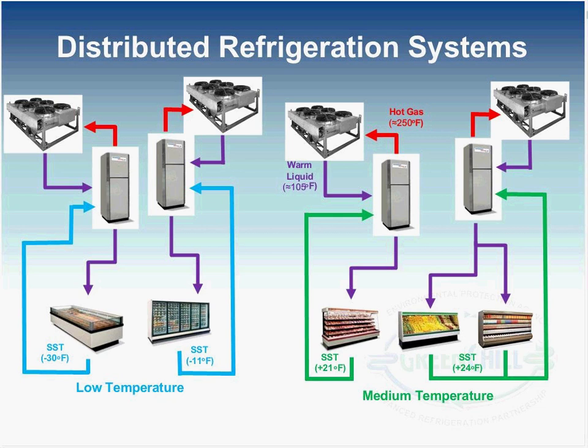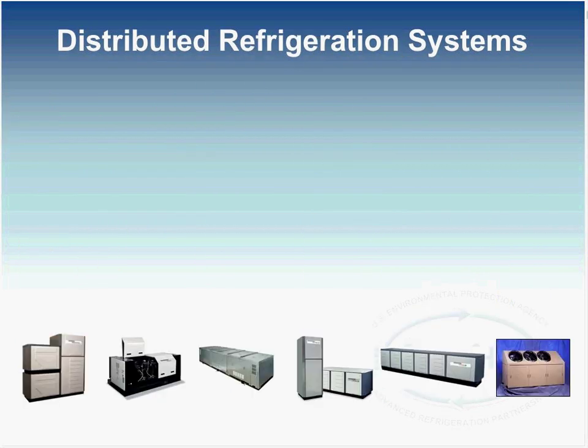And then likewise on the right-hand side, on the medium temperature, this is just showing an extreme where you have a 3-degree difference. But if you have a lot of meat cases or other cases that are running slightly colder than your produce or dairy cases, it does make good sense to put that on an individual unit. And again, the units that are operating at the warmer suction temperature would consume less energy than those running at the lower suction temperature. So this kind of gives you an idea about how the systems would be connected to the various different loads in order to improve energy operation of the unit.